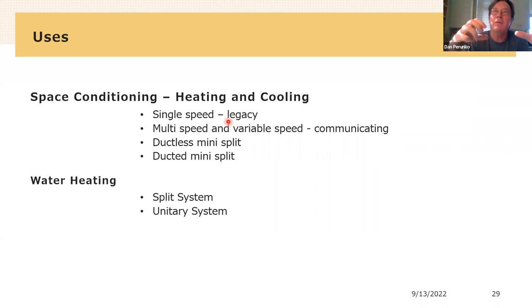There's all the things that I talked about already, right? Like refrigeration and dehumidification. But from our perspective, the two important uses we need to talk about are space conditioning and water heating. And under space conditioning, we have the two machines that I just showed you, which are single speed or two speed legacy machines. And so legacy essentially means that the control wiring is a series of somewhere between 3 and 8 circuits. And the circuits are all on-off switches, right? If they're powered, the circuit board receives that signal and it does something. If they're not powered, the circuit board's not receiving the signal and it does something else. They're just on-off commands.